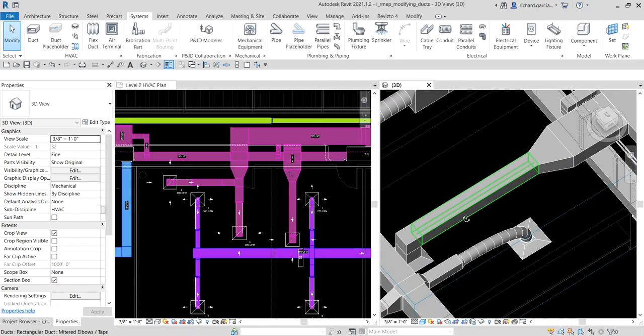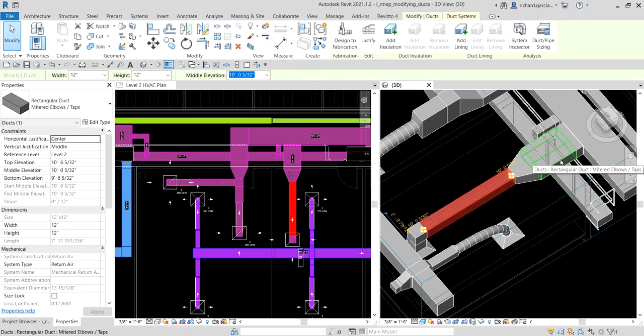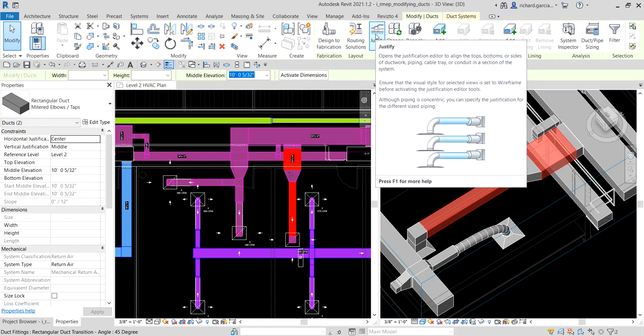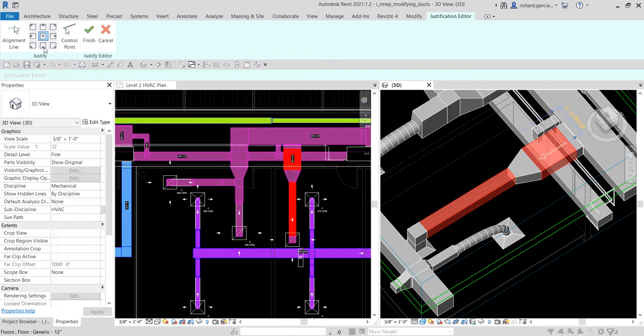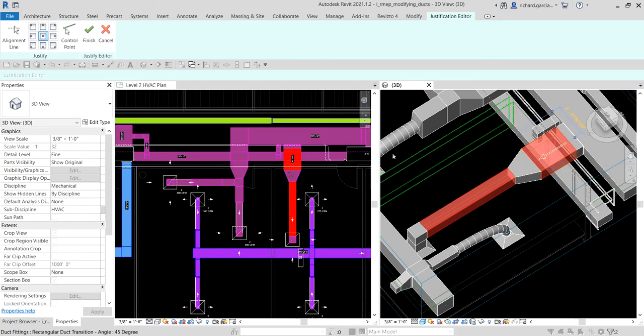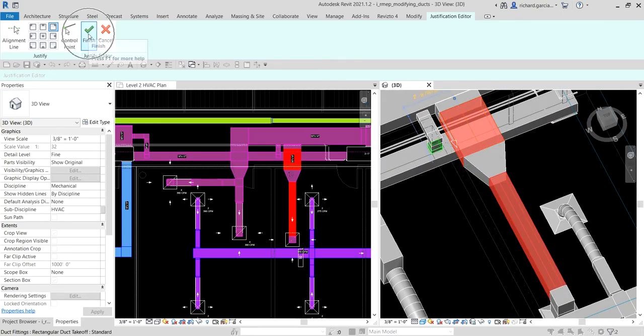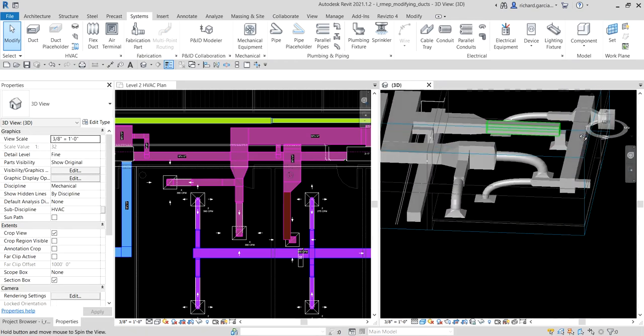You can also change the justification of your duct. Click a duct, hold Ctrl and click another duct, then select the Justify option — it opens the Justification Editor to align the tops, bottoms, or sides of ductwork, piping, cable tray, or conduit. Currently it's at Middle Center. I'll select Top Right — you can see the arrow showing the new alignment. Click Finish to apply it.